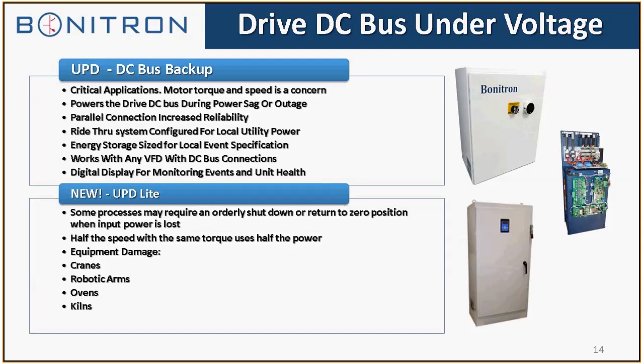Once again, the parallel connection. One of the advantages is that we will look at the utility power spec for that particular region, and we can size the energy storage to exactly the specification, whereas with an online double conversion UPS, usually they start at 5 minutes, and you may only need seconds or even just cycles of ride-through. So when comparing solutions, you have to keep that in mind. It's very important that we determine the specification before we actually provide a solution.